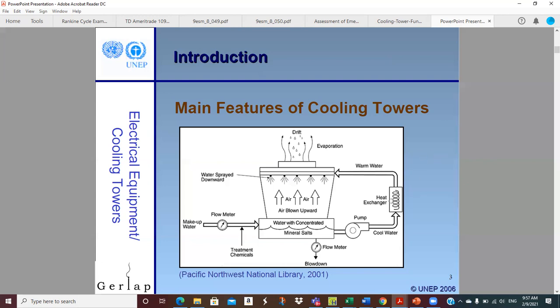But anyway, so we have some sort of a heat exchanger. We got some kind of a heat load that we're going to have to cool away. And so, our cold water falls down into the bottom called the well or the basin at the bottom. So this is the water that's fallen down through the tower. So it's cool. If we were to pick a number, we would probably say, I'm going to assume that's 85 degrees at design, because that's a pretty standard number. But it doesn't have to be. It could be 100 degrees. It's just whatever the system designer spec'd it out to be based on the process load and the size of the tower.